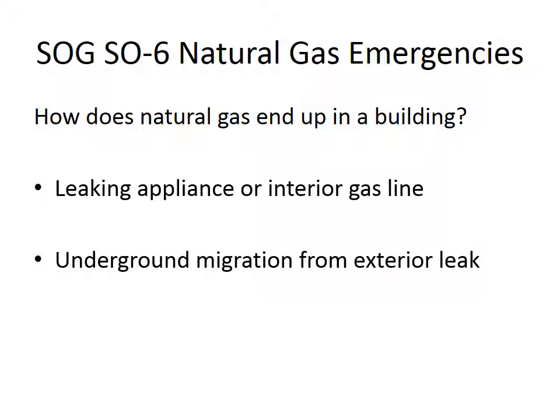And the thing to keep in mind about underground leaks is, well, what do we know about natural gas? Natural gas is colorless, odorless. The only reason it has an odor that we smell, that rotten egg smell, is because that's an odorant that is added to it to help identify when there's a leak. But when you have that exterior leak from the ground, that odorant can be stripped from the gas. So it might be making its way into the building with either a very different smell or no smell at all. Okay, so just something to keep in mind.